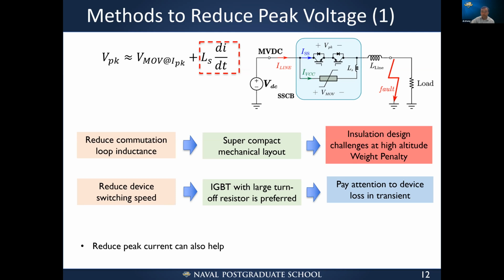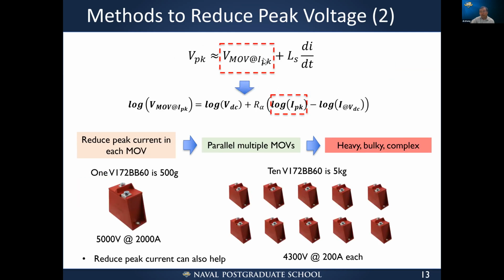That can also help. So if we are talking about the clamping voltage of the MOV, these are the equations we can use to estimate the MOV's peak voltage. The DC bus voltage we cannot change, so we either change the peak current, or change the leakage current in the steady state. If you want to reduce the peak current, the easy way to do it is, instead of using one MOV, we can put multiple MOVs in parallel.